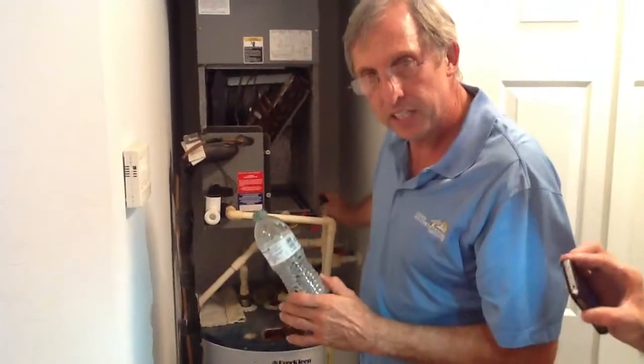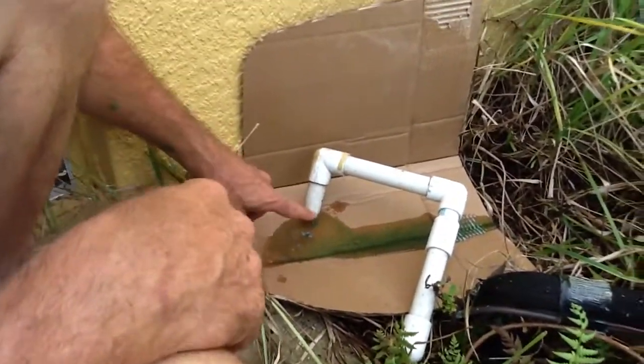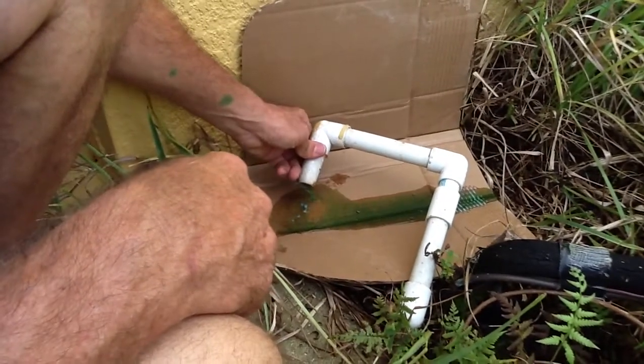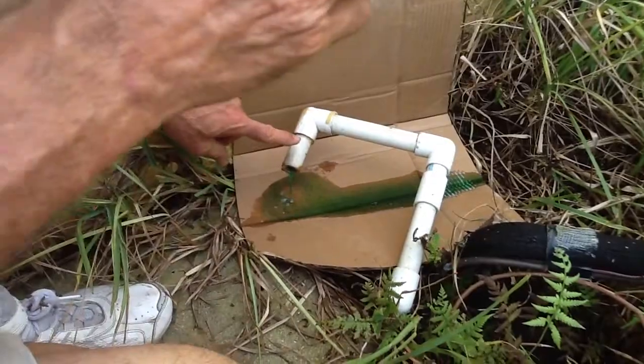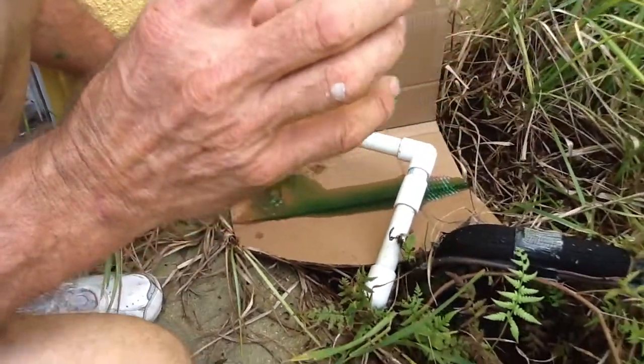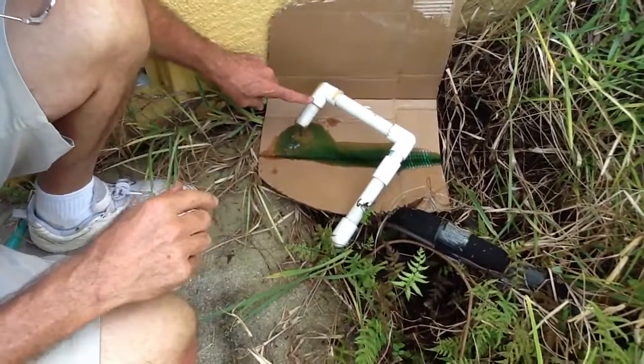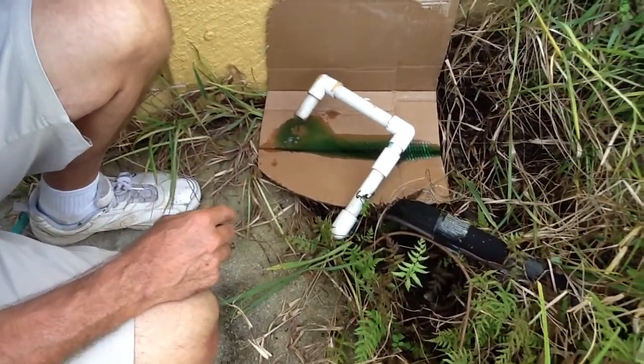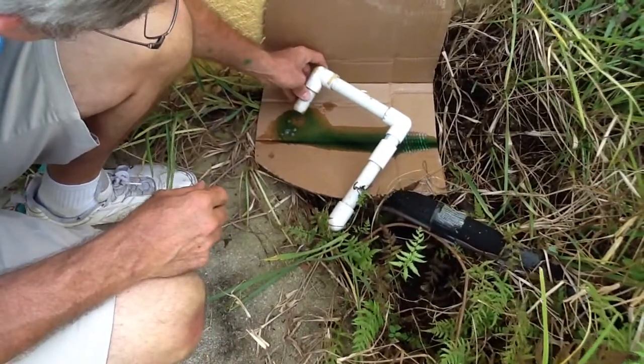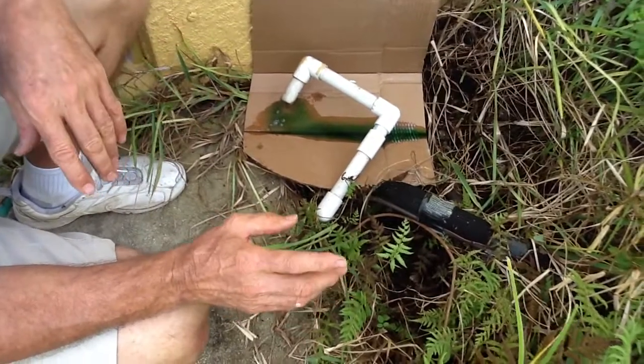Okay, let's go outside and see how we're doing. Folks, here's what you got — you see that green water? I timed this. We put three 16-ounce bottles of water into the drain because it was about 100 feet. So now I know I have flow from my air handler to my drain. See this green coloring? So I don't have to worry about this lady — she's in good shape.